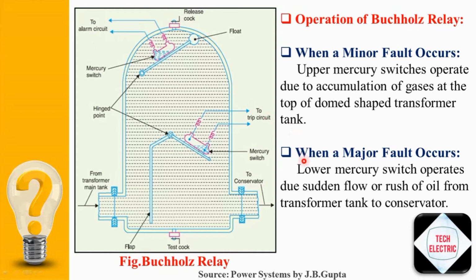Now, when a major fault occurs in the transformer unit, there is a sudden flow or rush of transformer oil from the transformer tank towards the conservator. Here, the flap is placed such that it senses a sudden violent movement of oil from the transformer tank towards the conservator. So, the flap tilts the mercury switch, which operates the trip circuit to switch off the circuit breaker related to the transformer, and the transformer unit is protected against the fault.